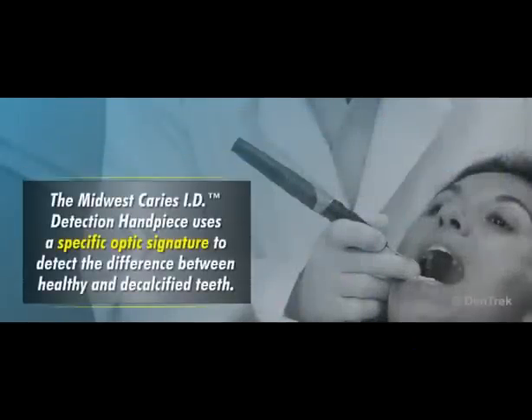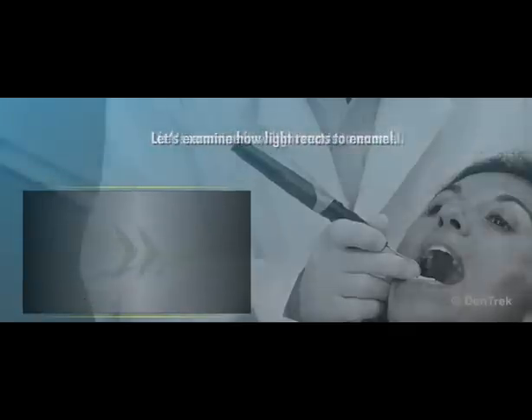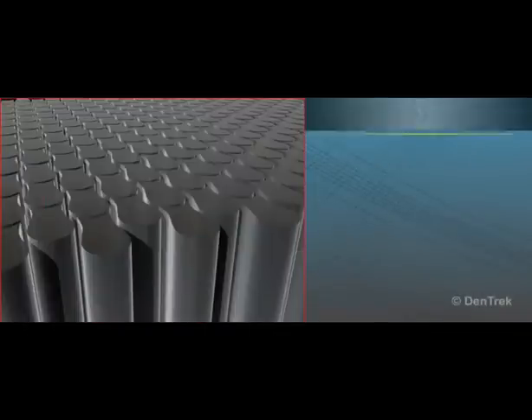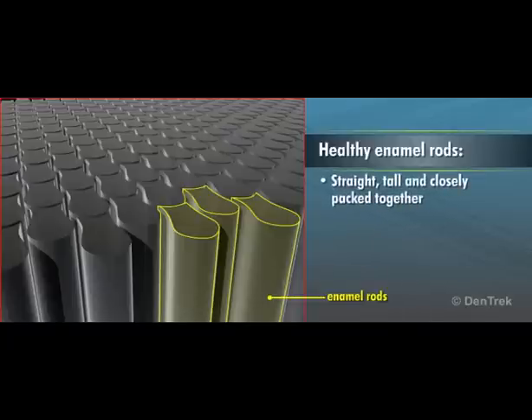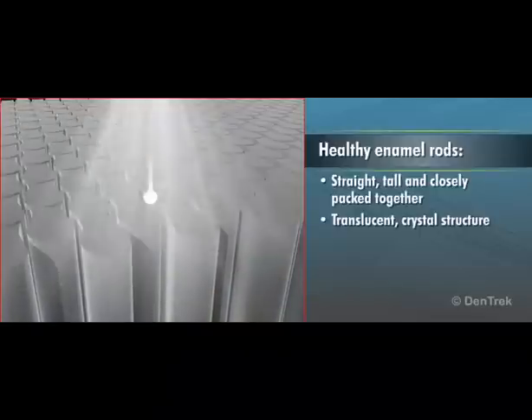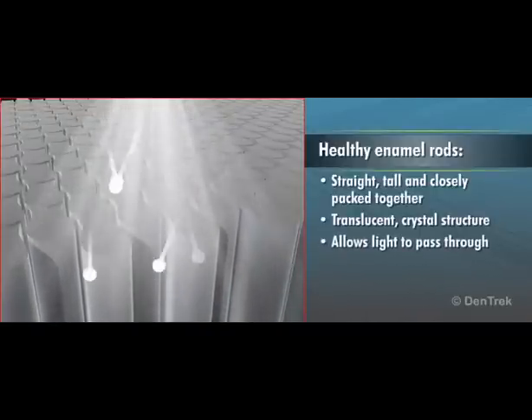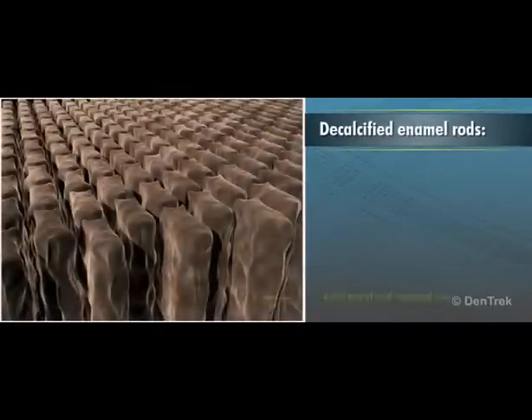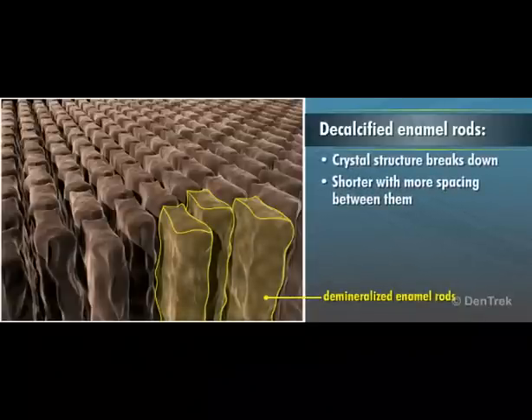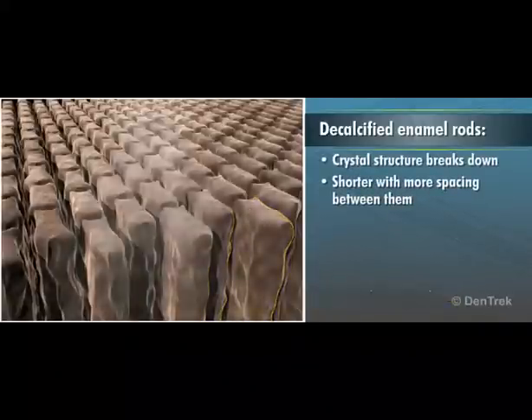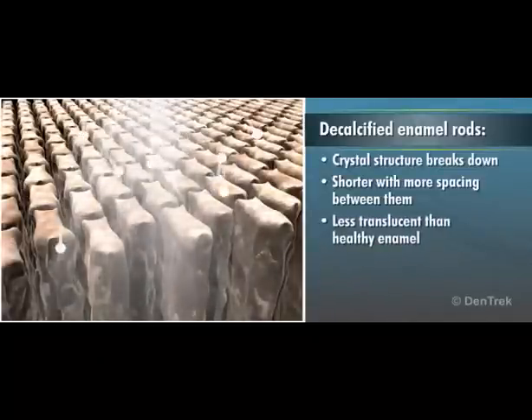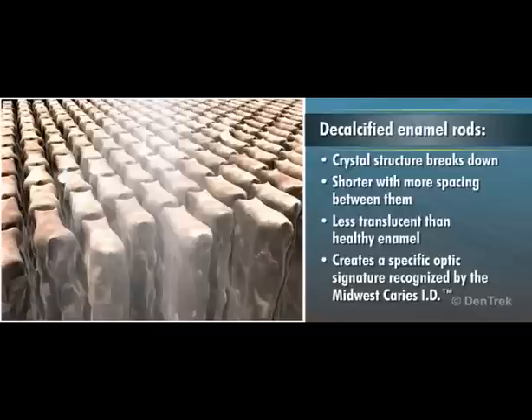The Midwest Caries ID Detection Handpiece uses a specific optic signature to detect the difference between healthy and decalcified teeth. To understand how this works, let's examine how light reacts to enamel. The enamel structure of a tooth is made up of enamel rods. When healthy, these rods are straight, tall, and closely packed together in a translucent, crystal-like structure that allows light to pass through. When decalcification occurs, this crystal structure breaks down, shortening the rods and allowing more spacing between them. As a result, the tooth becomes less translucent than healthy enamel. This creates a specific optic signature that is recognized by the Midwest Caries ID Detection Handpiece.